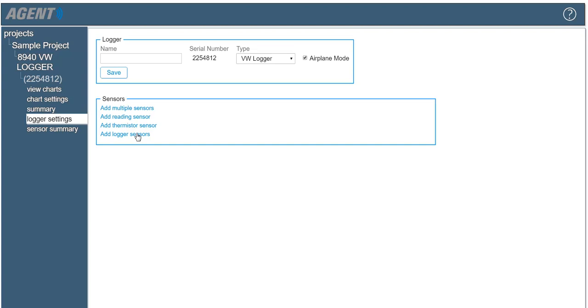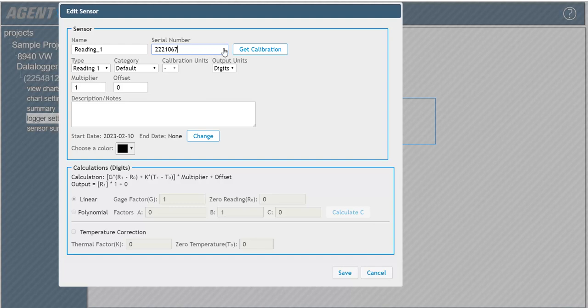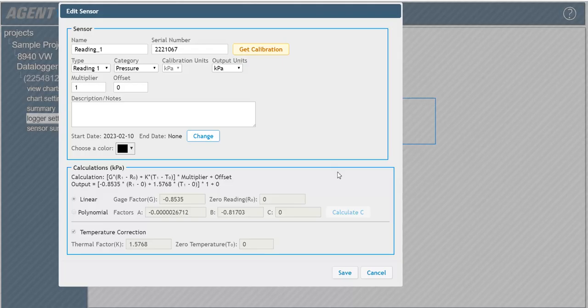For this demonstration, we will set up a reading sensor for a vibrating wire gauge. Start by entering the serial number of the sensor. Click the Get Calibrations button to retrieve the calibration factors and other pertinent information about the sensor from Geokon's online calibration database. This feature is compatible with most sensors manufactured after 2016.